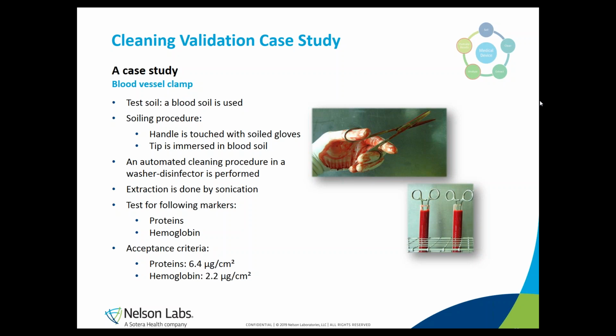To have the test sensitive enough to quantify residues of proteins and hemoglobin below the provided acceptance criteria, we will have to calculate a maximum extraction volume that can be used, based on the surface area of the device itself, the acceptance criteria provided by our sponsor, and the limit of quantification of the analytical technique that we will use to measure remains of the particular marker in the extract.